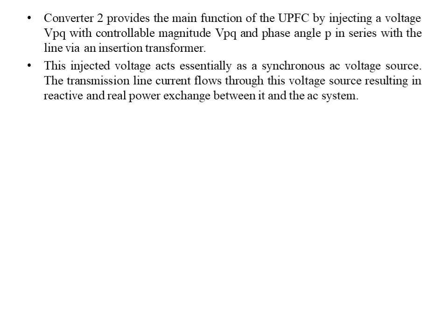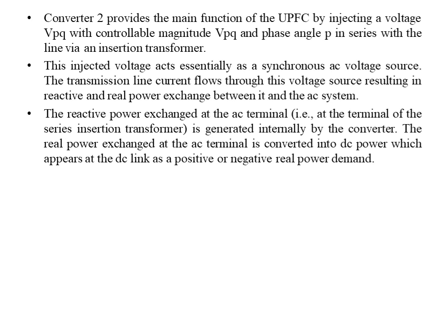By injecting the voltage, Converter 2 generates reactive and real power, since current flows through the transmission line and we inject voltage — power being the product of voltage and current. Depending upon the magnitude of voltage injected into the transmission line, the magnitude of reactive and real power is determined. The reactive power exchanged at the AC terminal of the series insertion transformer is generated internally by the converter. The real power exchanged at the AC terminal is converted into DC power, which appears at the DC link as positive or negative real power.